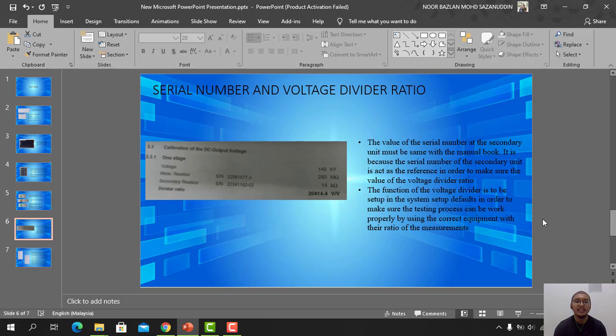So for this testing, we will use the secondary resistor unit, which has a voltage divider ratio of about 20414.4. The function of this voltage divider is to be set up as default in the system to make sure all testing processes can work properly using the correct equipment and ratio of measurement.